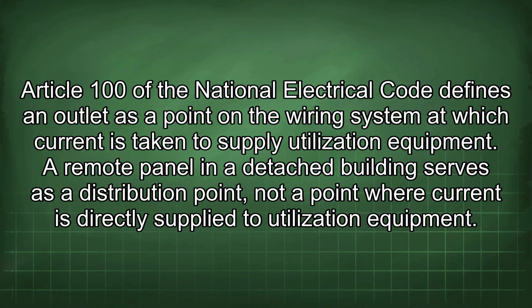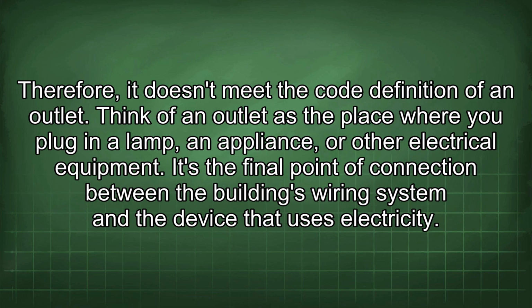Article 100 of the National Electrical Code defines an outlet as a point in the wiring system at which current is taken to supply utilization equipment. A remote panel in a detached building serves as a distribution point, not a point where current is directly supplied to utilization equipment. Therefore, it doesn't meet the code definition of an outlet.